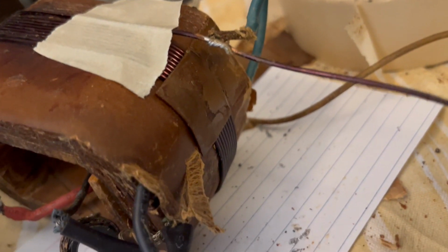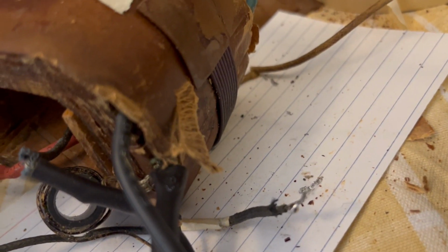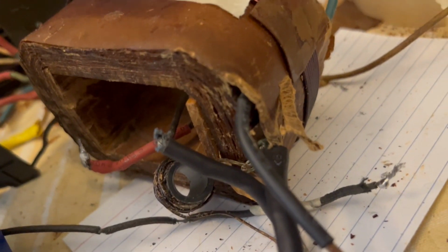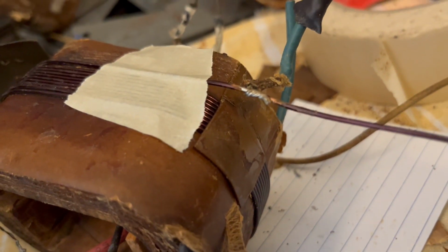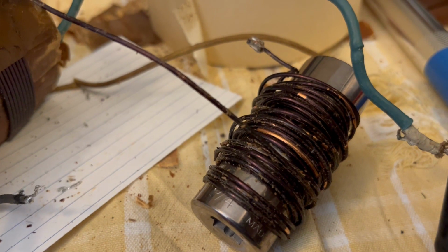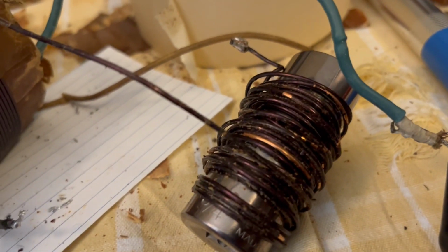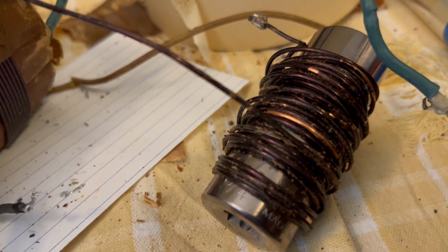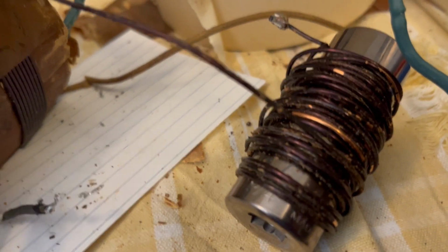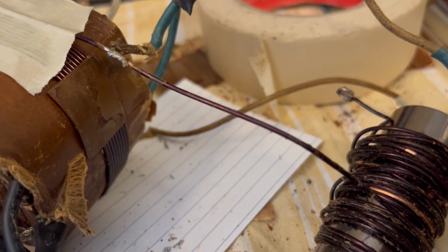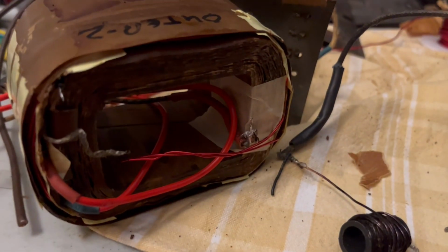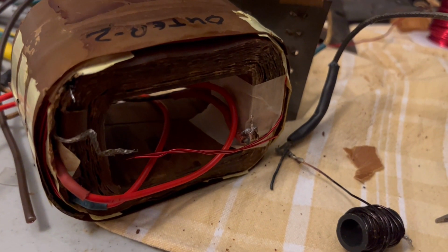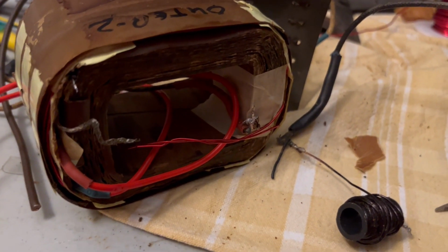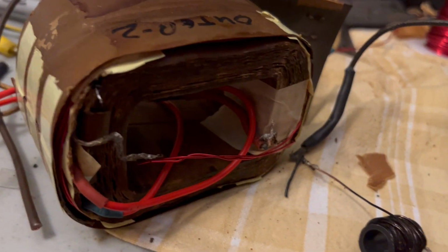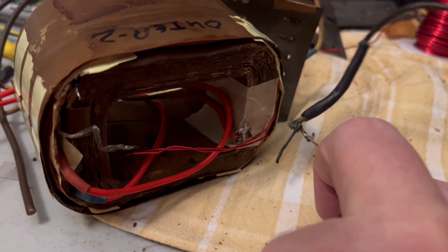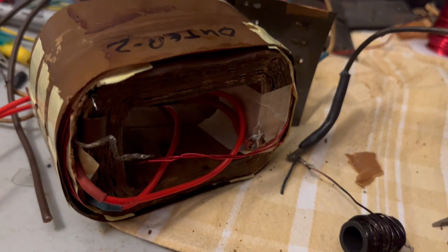And although I couldn't see exactly where that short had been, I began planning to rewrap the coils, making sure that nothing shorted along the way. But unfortunately, I would have to wait until I received a shipment of new magnet wire because the insulation was just too far gone on the coils I had removed to consider reusing. Well, after getting two of the windings back on, I was starting to work on the third one when catastrophe struck on this thing. And that is that this wire right here broke off. This black lead right there.